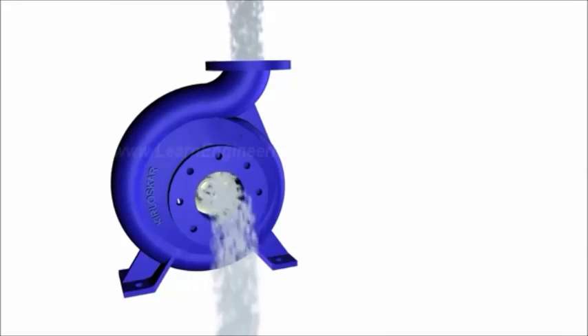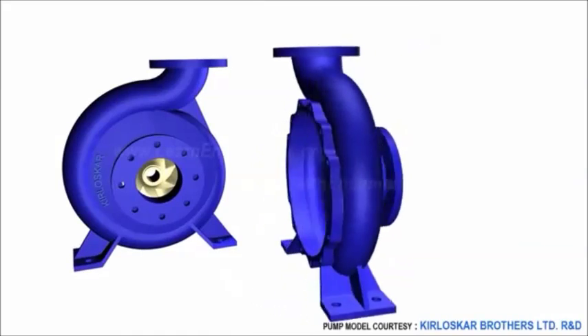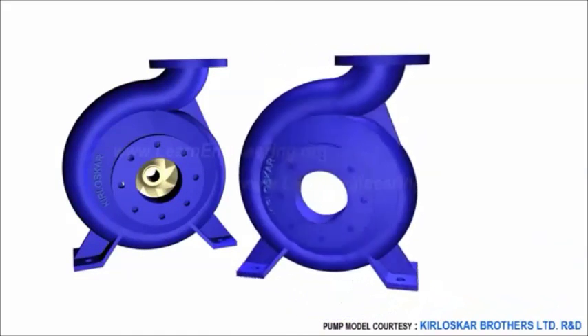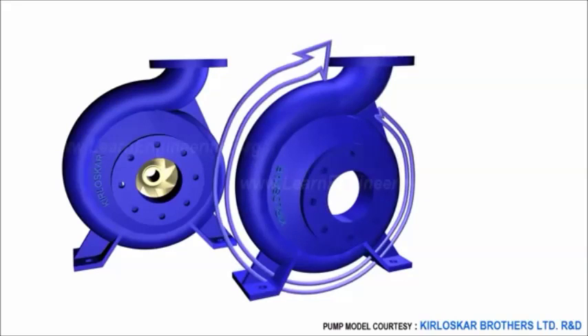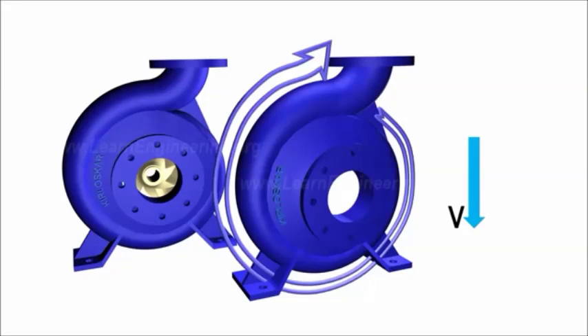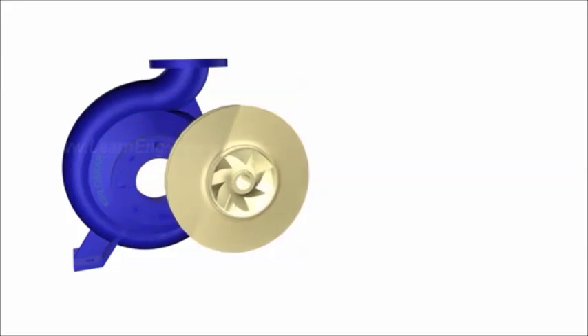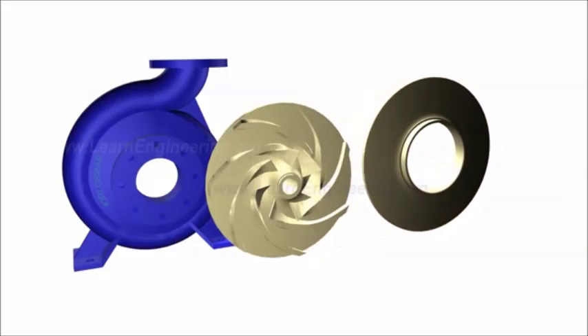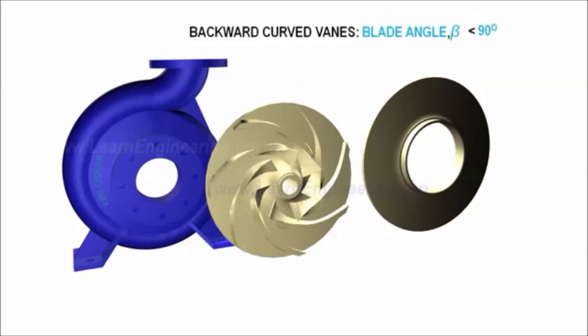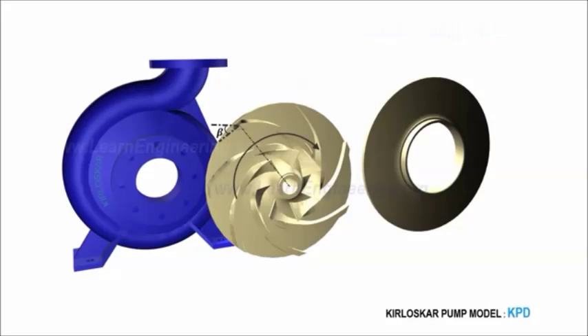Here you can note one specialty of the casing. It has increasing area along the flow direction. Such increasing area will help in accommodating the newly added water stream and will also help in reducing exit flow velocity. Reduction in flow velocity will result in an increase in static pressure, which is required to overcome resistance of the pumping system. Here you can see more details of vanes inside the impeller. They are backward curved vanes with state-of-the-art eye configuration. This vane is extracted from a Kirloskar pump model.